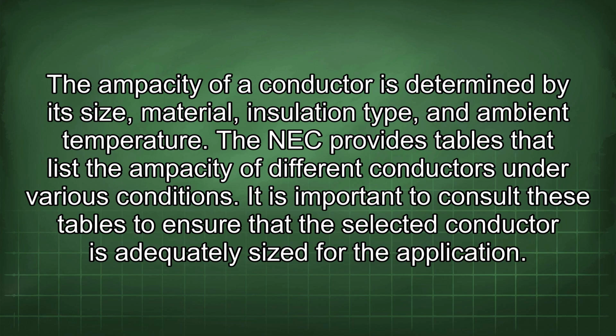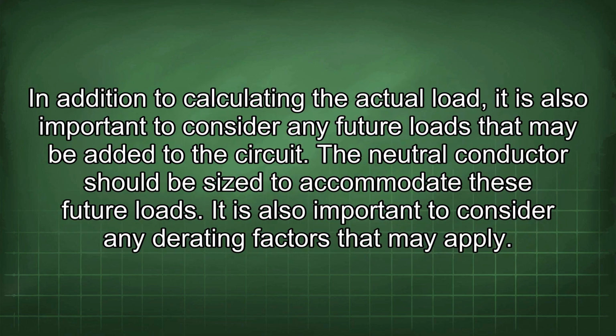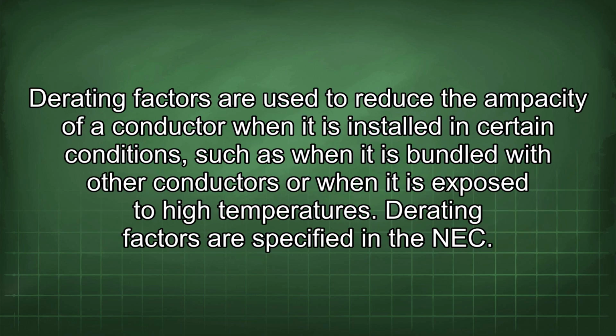The NEC provides tables that list the ampacity of different conductors under various conditions. It is important to consult these tables to ensure that the selected conductor is adequately sized for the application. In addition to calculating the actual load, it is also important to consider any future loads that may be added to the circuit. The neutral conductor should be sized to accommodate these future loads. It is also important to consider any derating factors that may apply. Derating factors are used to reduce the ampacity of a conductor when it is installed in certain conditions, such as when it is bundled with other conductors or when it is exposed to high temperatures. Derating factors are specified in the NEC.